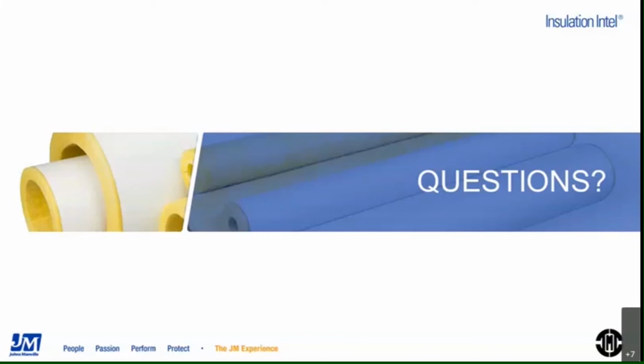All right, thank you. Greg, the next question is for you, and that is: is there a spot on the submittal sheet that says listed and labeled for use in plenums over PVC and PPR piping? No, that would be a direct submittal for that type of product for that situation. That would be a line item on that submittal, what I meant. So you can do that, 2550, you put it in your submittal, this will cover your plenum rating. We do those submittals all the time like that.